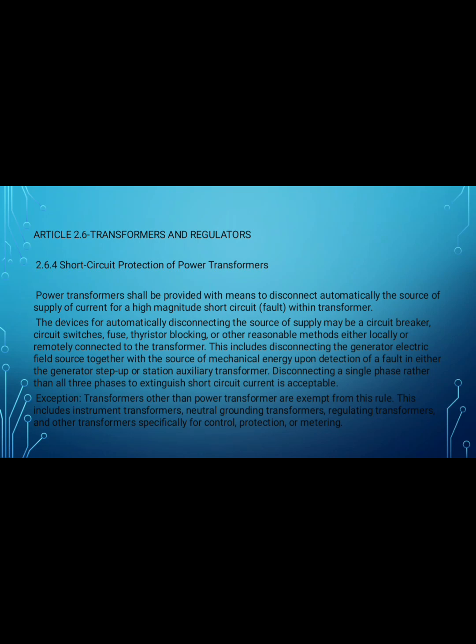This includes disconnection of the generator electrical field source together with the source of mechanical energy upon detection of failure in either the generator step-up or station auxiliary transformer. Disconnecting a single phase rather than all three phases to extinguish short circuit current is acceptable. Exception: Transformers other than power transformers are exempt from this rule. This includes instrument transformers, neutral grounding transformers, regulating transformers, and other transformers specifically for control, protection, or metering. Short circuit protection of power transformers refers to the method used to protect the transformer from damage caused by short circuit.